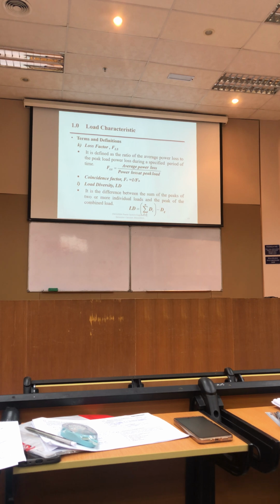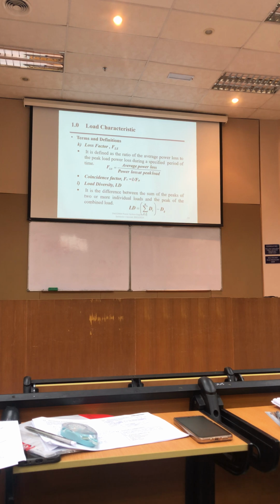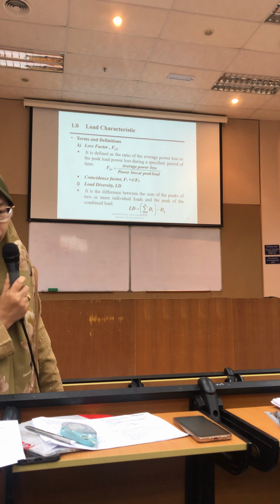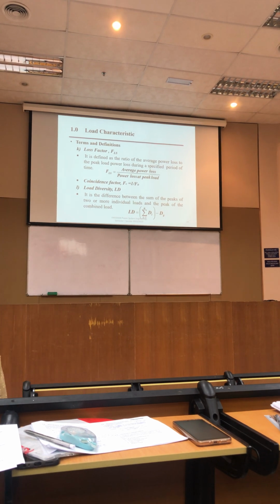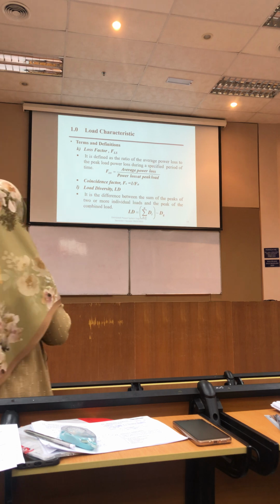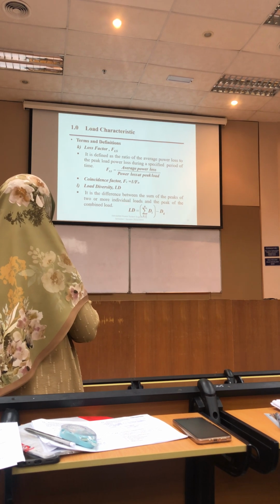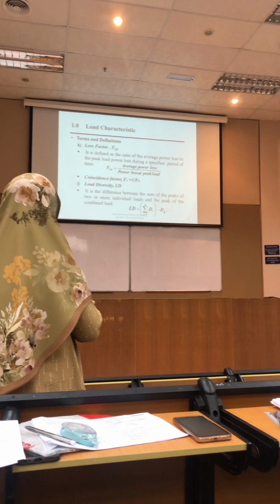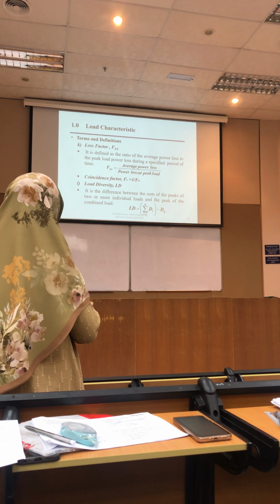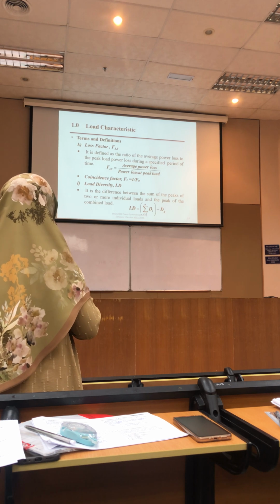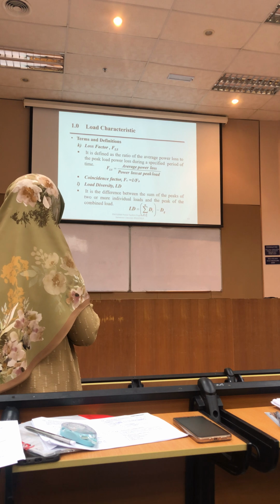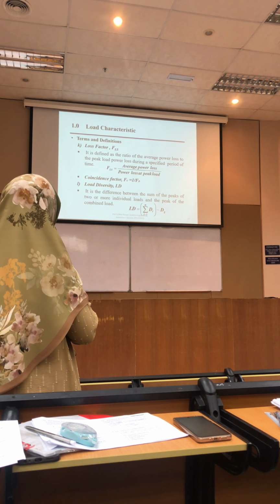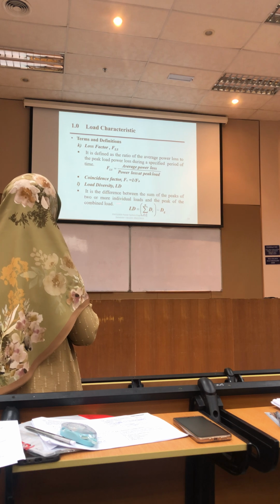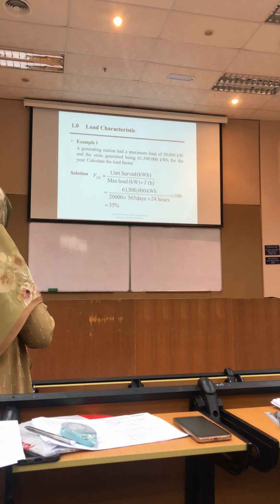So this is the coincidence factor. FC equals to 1 over FD. Okay. FD apa dia, student? FD apa dia? Okay, good. Diversity factor. It is the difference between sum of the peaks of the two or more individual loads and the peak of the combined load. That's what we call as diversity factor by using this formula. The summation of 2 or more individual loads, okay, minus DG, the peak of the combined load.